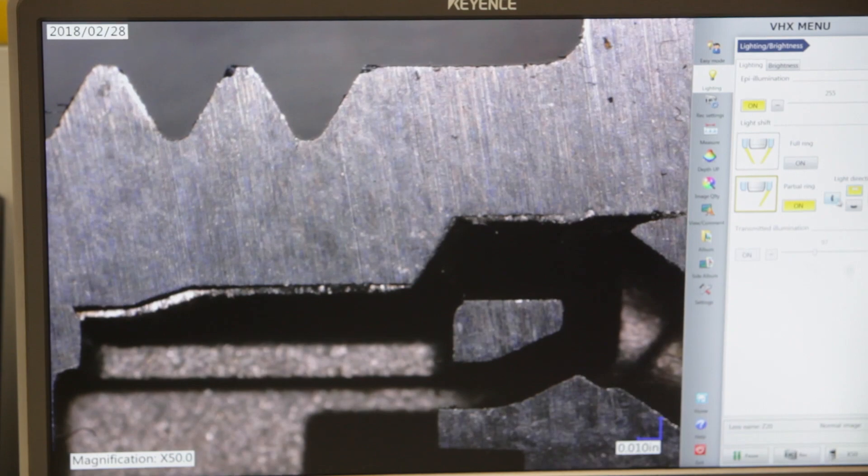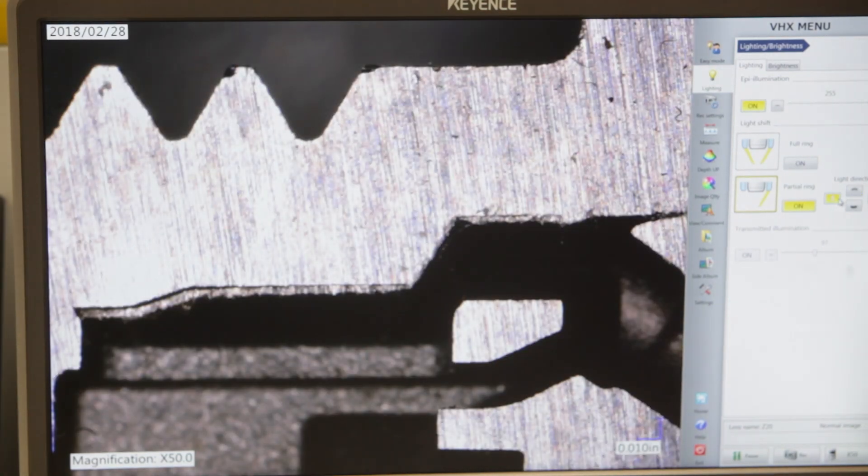Another important feature of this microscope that makes it so valuable is the ability to adjust the lighting. You have reflection removal which will take out any reflections that you have on these very shiny parts, as well as the ability to change the direction of the lighting. You can turn on different banks of LEDs to mimic putting lights at different angles.